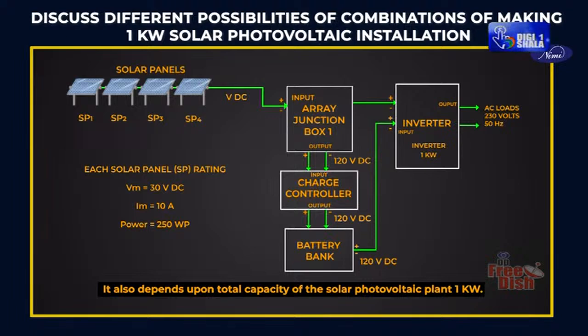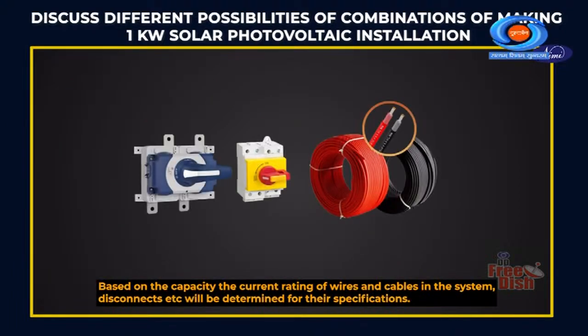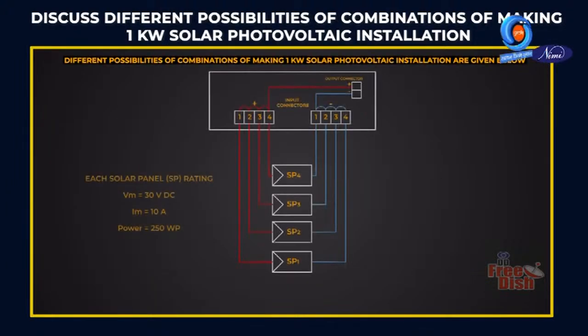It also depends upon total capacity of the solar photovoltaic plant, 1 kilowatt. Based on the capacity, the current rating of wires and cables in the system, disconnects, etc. will be determined for their specifications. Different possibilities of combinations of making 1 kilowatt solar photovoltaic installation are given below.